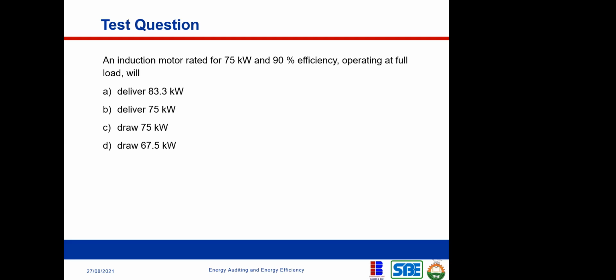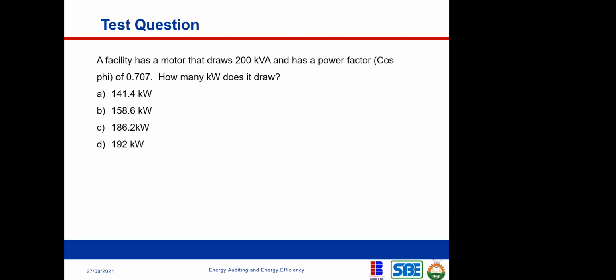So when these conditions are met, when it's operating at full load at 90% efficiency, which is the rating that has been inscribed on the nameplate, then the output will actually be 75 kilowatts. Is that okay now? Or is this still confusing? Okay. It's okay now. Okay.